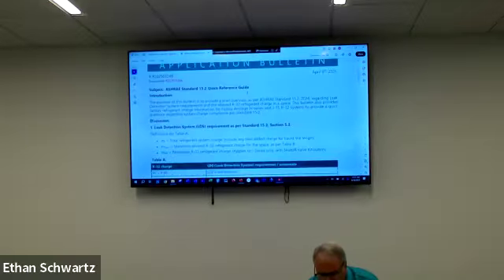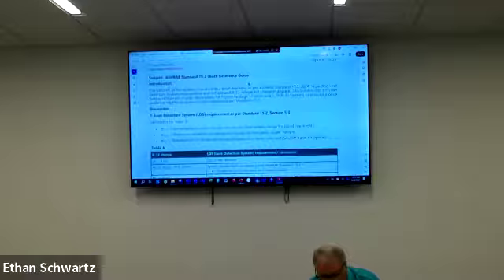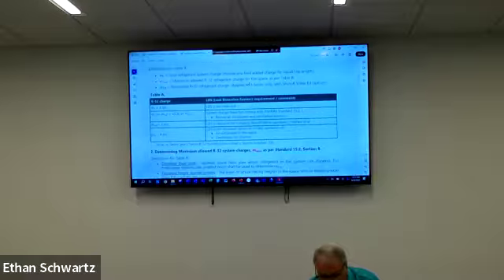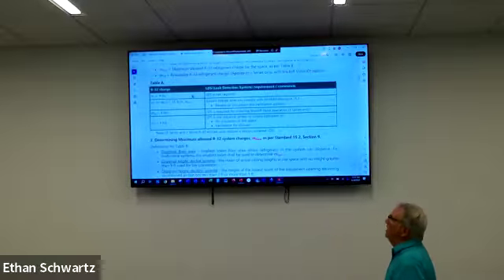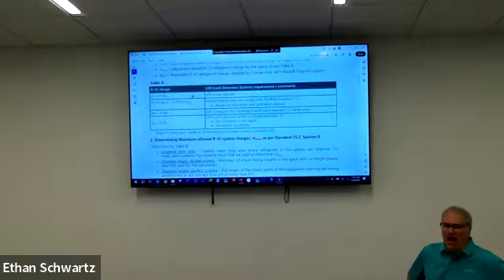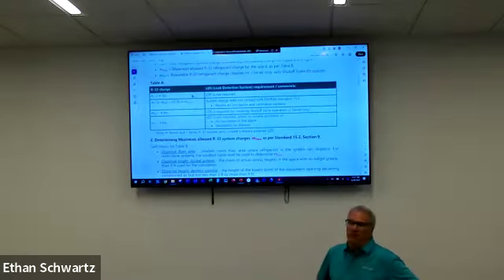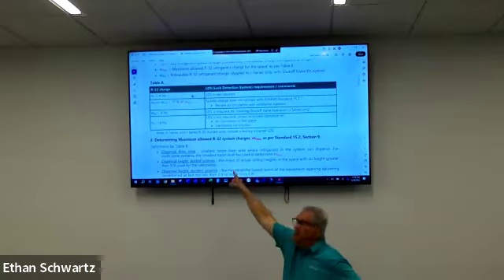But then we have boiled that down to the H and J series residential. 15.2 is the residential side of the standard, and what's really required and what's going on here. And if you look at a submittal for one of our H series systems, you will see that most of them, contractors are not going to have to worry about any leak detection systems because they are below 4 pounds.